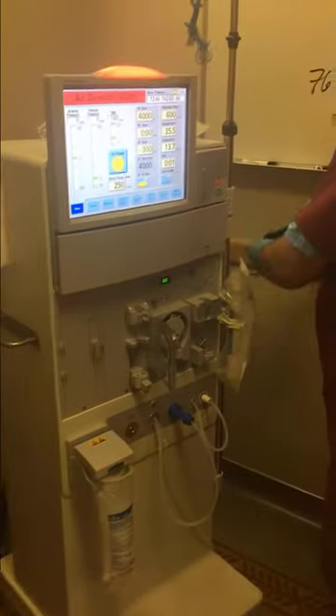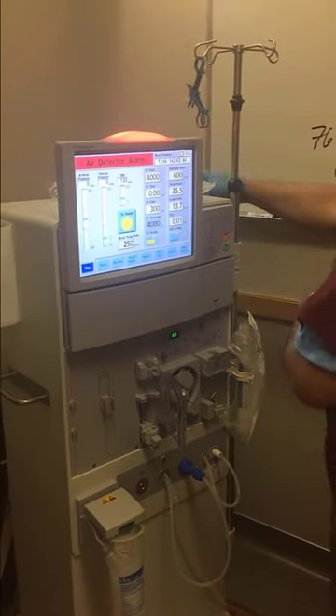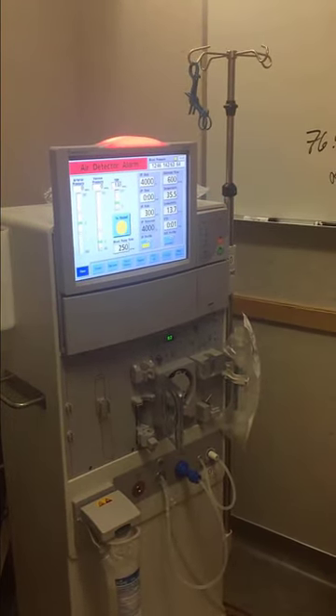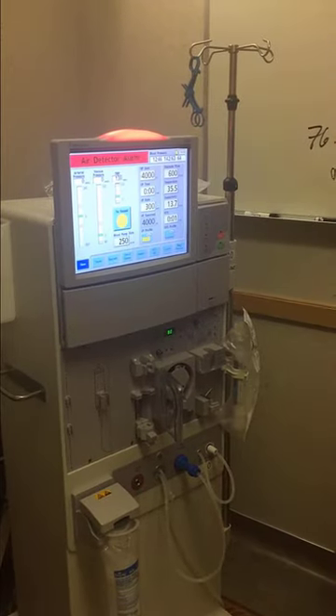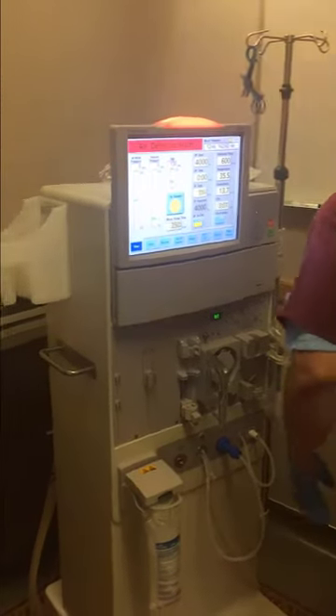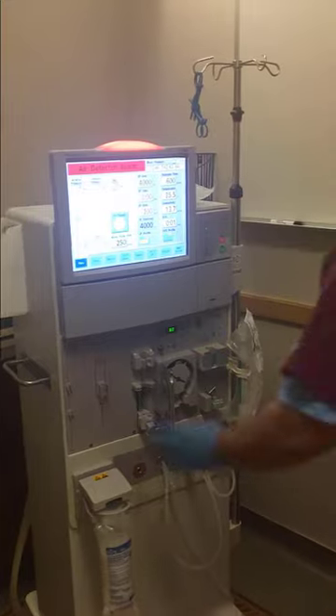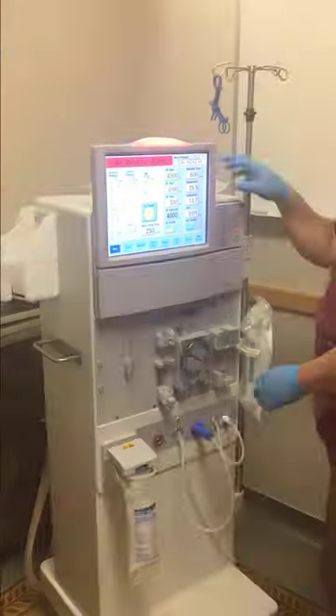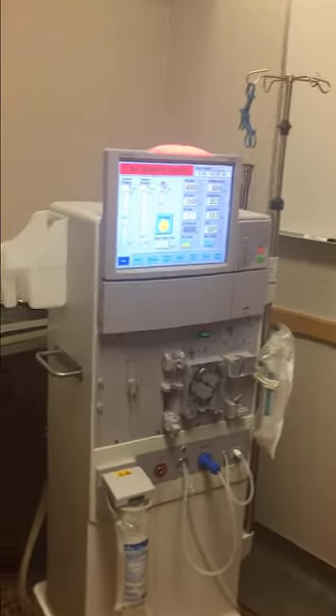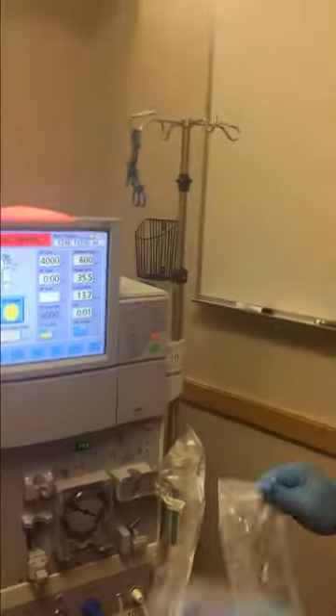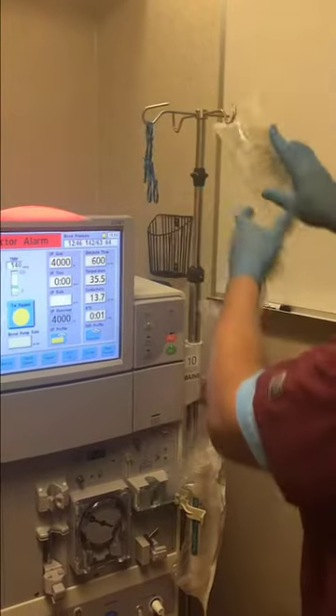If you don't already have a bicarb bag on the machine, you can add one now and it will begin priming. Your conductivity won't come up to the proper levels of 13.5 to 14.5 until the bicarb and acid are all plugged in and the water is on. For priming, the water needs to be on.